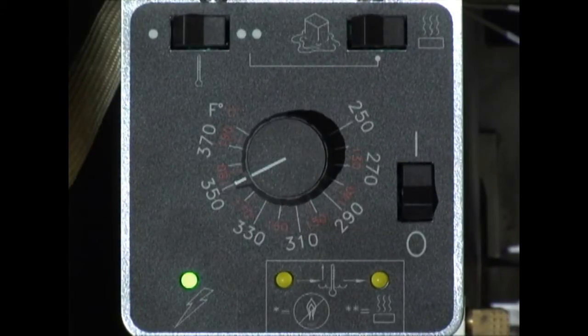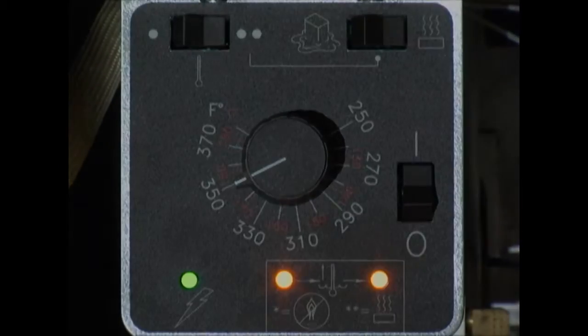There are 3 LED lights on the front of the controller. The first indicator, which is a green indicator, shows that the control is turned on. The second is a heat demand indicator. This LED shows that the control is demanding heat. The third is the heat feedback or fault indicator. This indicator shows when the appliance is heating in response to a heat demand. Under normal conditions, this light will follow the heat demand indicator. This indicator is also used to flash conditions for probe faults, drain valve open conditions, or boil out operations.